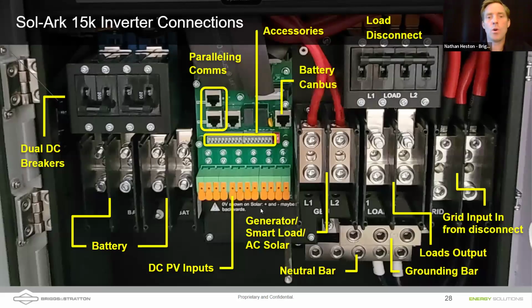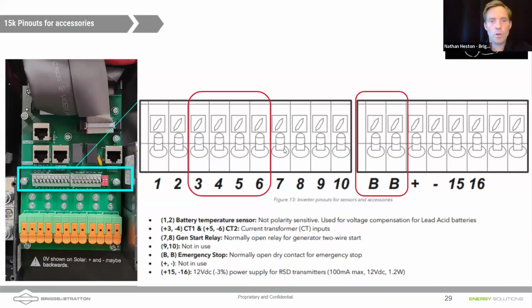So the MPPTs are there with those orange cam lock levers that you can see. And then the AC solar would come in through L1 and L2 on the generator port, the neutral bars down here at the bottom. If you are using AC coupled solar, you will want to have the CTs installed. The CTs get installed on the communications hub in that Sol-Ark inverter. So on that comms bar there, 3, 4, 5, and 6 are CTs.